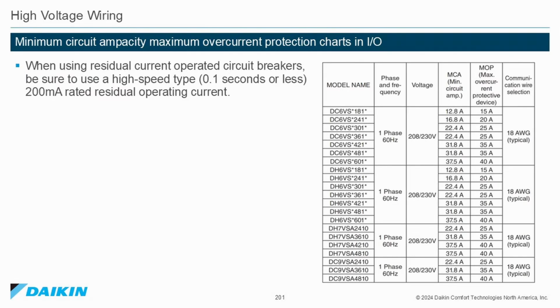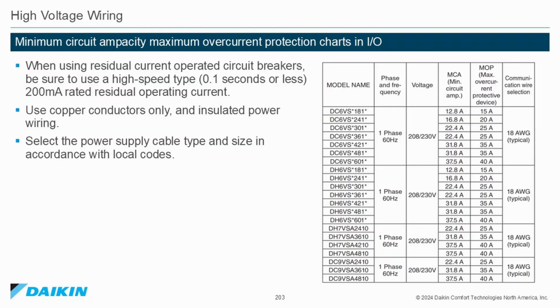Minimum circuit ampacity and maximum overcurrent protection charts are found in the installation operation manual. When using residual current operated circuit breakers, be sure to use a high-speed type, 0.1 second or less, 200 milliamp rated residual operating current. Use copper conductors only and insulated power wires. Select the power cable type and size in accordance with local codes.